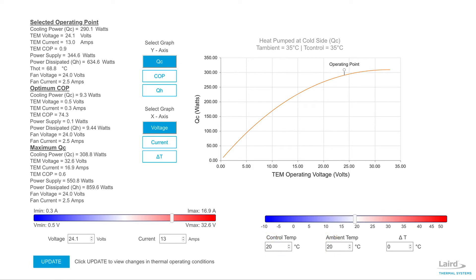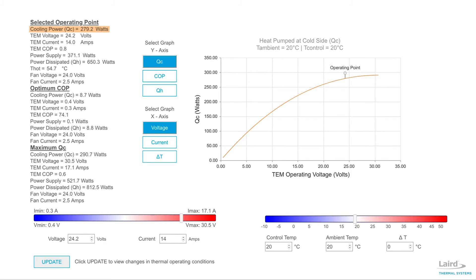With the drop in operating temperature from 35 degrees C to 20 degrees C, the cooling power dropped from 290 watts to 279 watts at 24 volts, which still meets the 240 watt spec with 39 watts of margin.